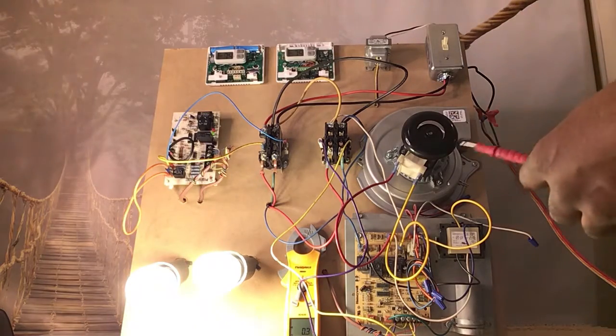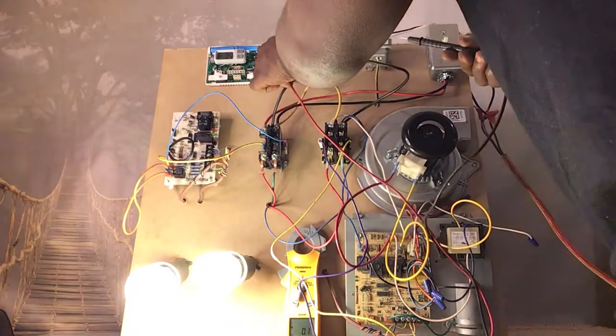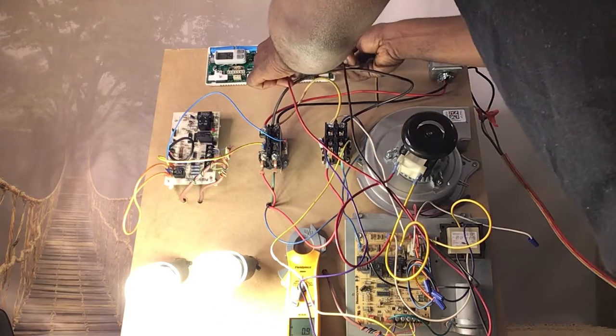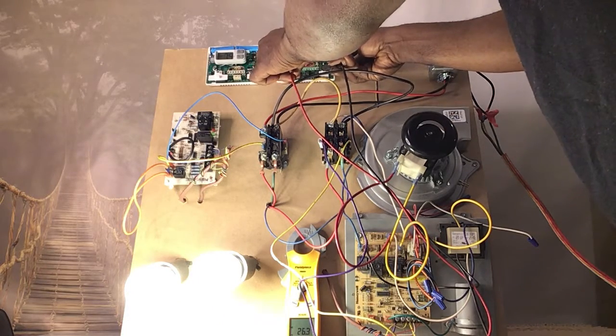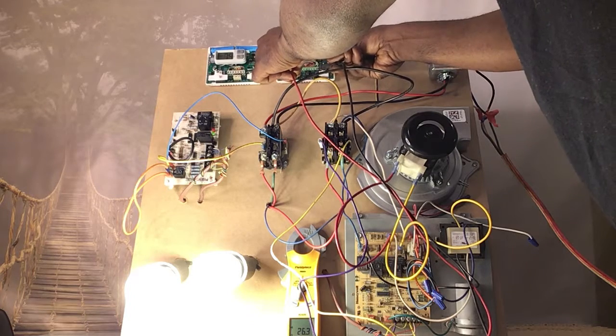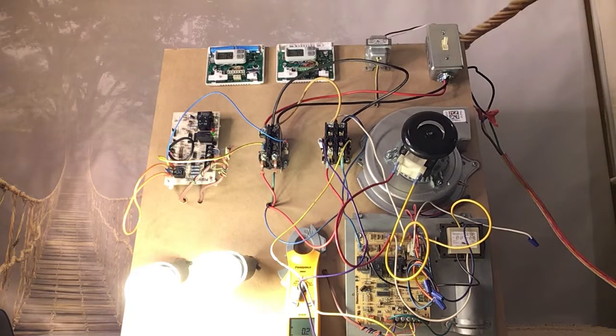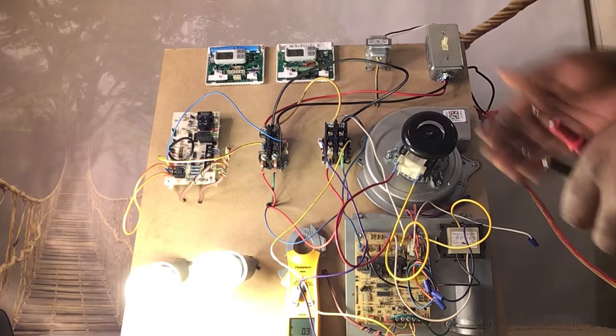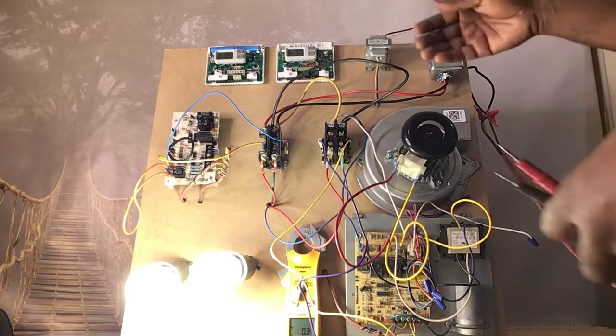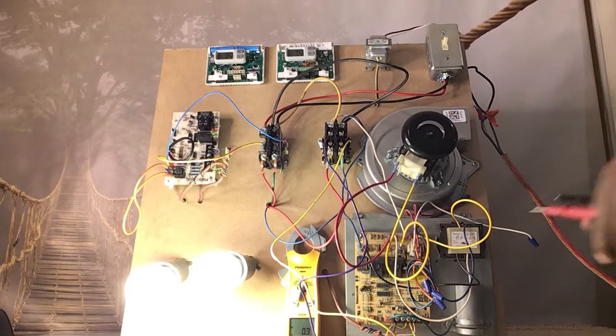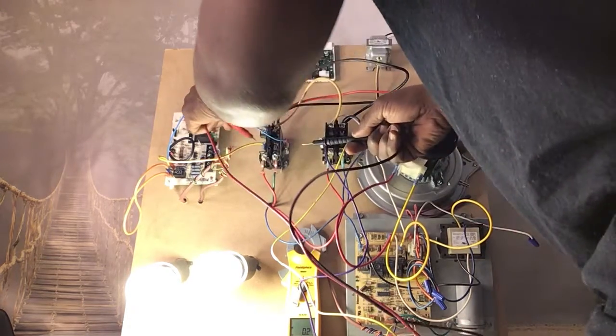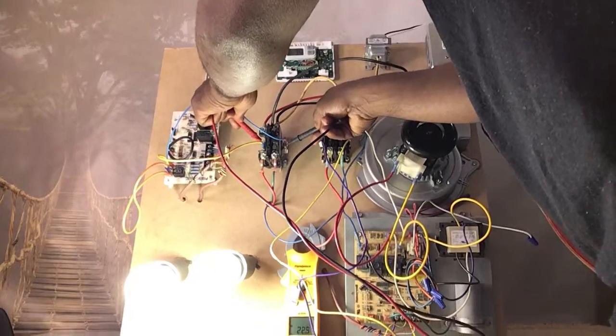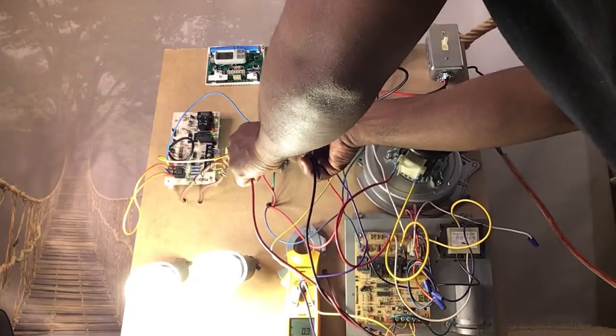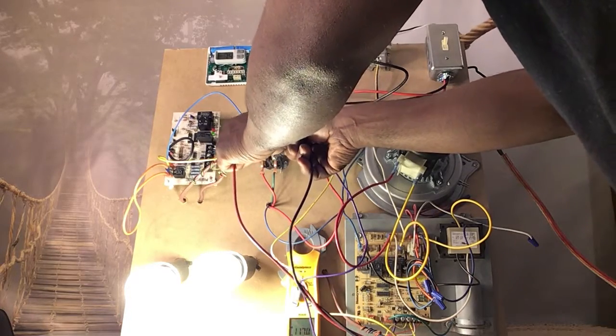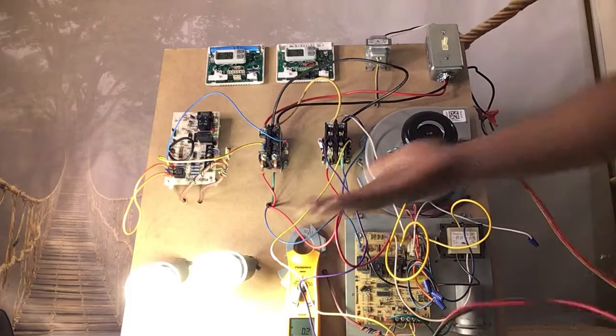So now from common to yellow, you should have 24 volts, right? 24 volts. Because your thermostat just registered that you want cooling, so it in turn shifted power from the red wire to the yellow wire in order to give you 24 volts to this coil. So now your coil will activate and it will transfer power, your 120 volts, from one side to the next, i.e. turning your lights on.